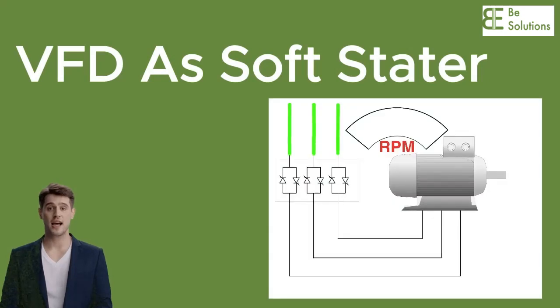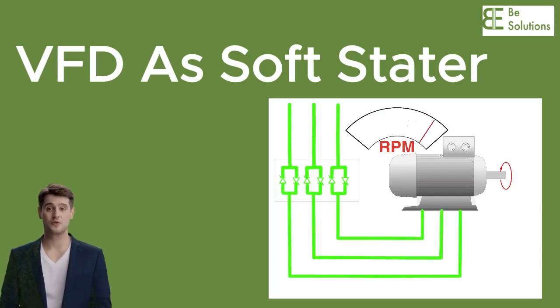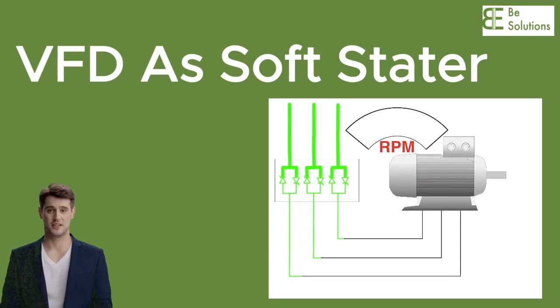Variable frequency drives, VFDs, serve as soft starters by allowing gradual acceleration and deceleration of electric motors, controlling speed through adjustable frequency and voltage. They minimize inrush currents, offer torque control, and enhance energy efficiency, providing a comprehensive solution for smooth motor operation and protection.